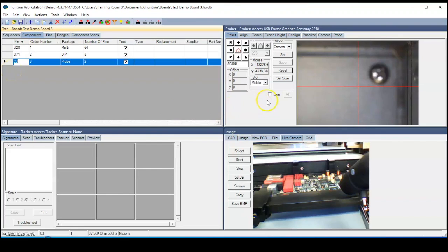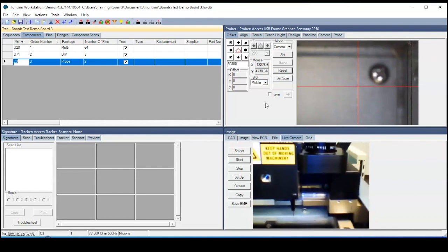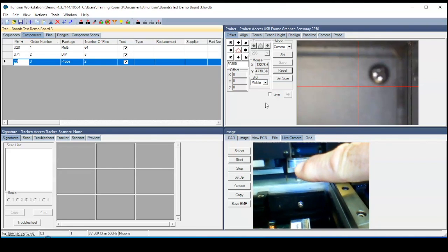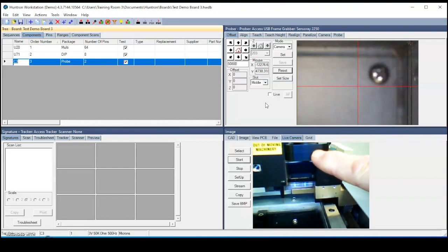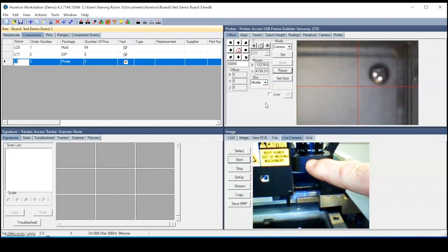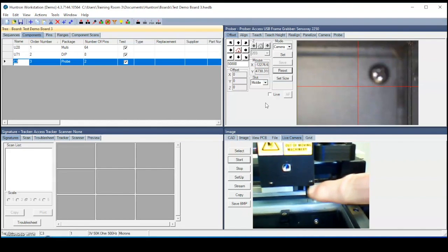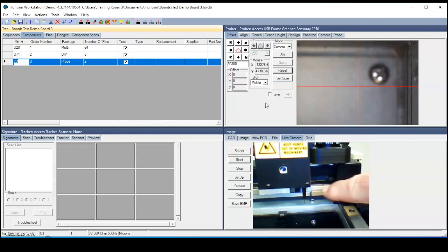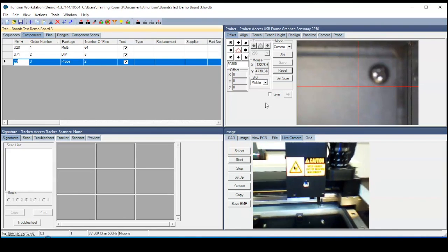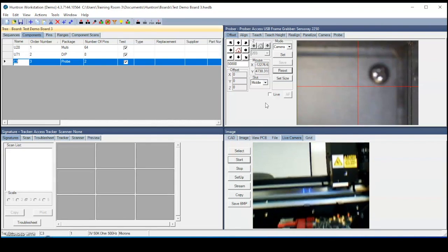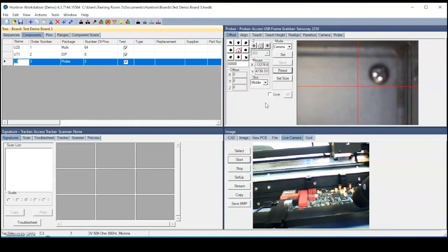Now before we can use the prober to accurately probe devices, we need to do what we call offset. And what offset is, let me grab my camera. You see the probe tip is right here, and the camera is to the right over here. So the software needs to know the distance between where the camera is looking to the probe tip. It needs to know this relationship distance. That way, when we teach a component location with the camera, we can put the probe precisely on that same point. So to do that, we use this offset tab in the prober pane.